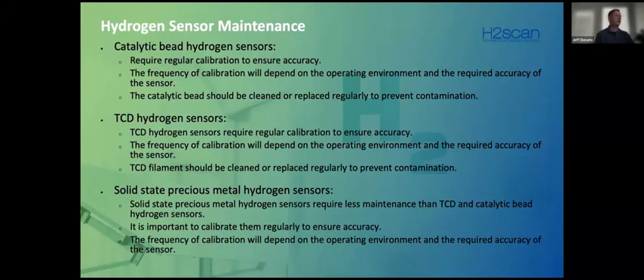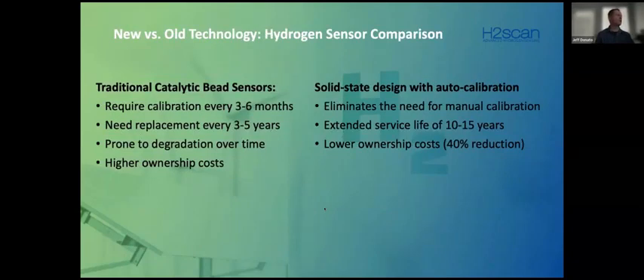However, there are some solid state technologies that basically will not require as much calibration or will auto calibrate by themselves. There are some TCD sensors as well that may not require calibration. They may require some bump testing, but also have a limited life, so you have to know when to replace them as well. So when you're selecting, just make sure you understand the specification and the maintenance requirements around those specifications. And again, this is just an example: a catalytic bead may require a calibration every 3 to 6 months and replacement every 3 to 5 years, and is consumed by its environment, where maybe a solid state sensor would not have to go through manual calibration and last a lot longer.